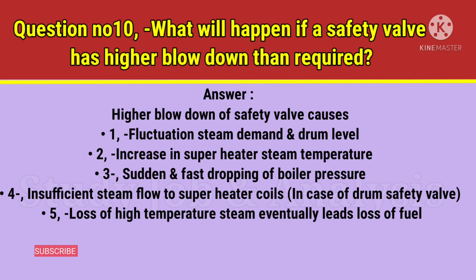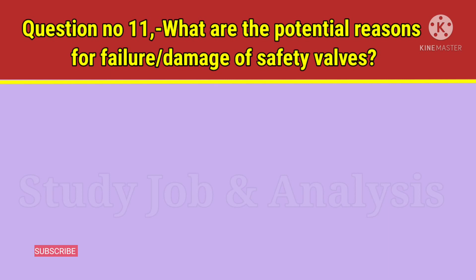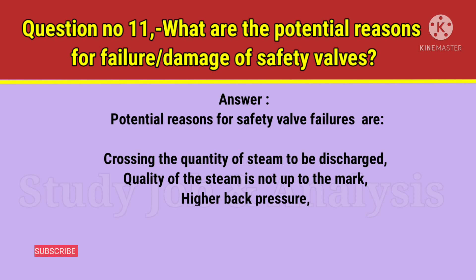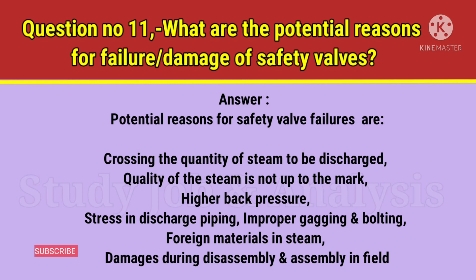Question number 11: What are the potential reasons for failure or damage of safety valves? Answer: Potential reasons for safety valve failures are: crossing the quantity of steam to be discharged, quality of steam not up to the mark, higher back pressure, stress in discharge piping, improper gagging and bolting, foreign materials in steam, and damages during disassembly and assembly in the field.